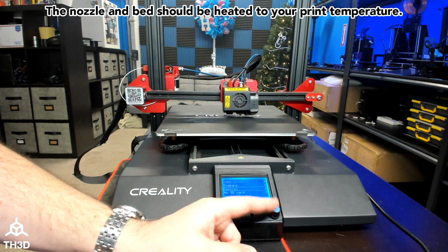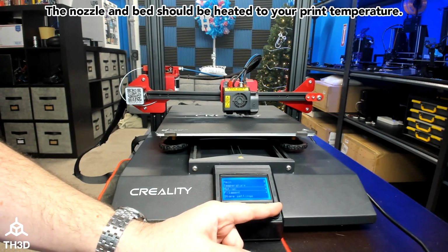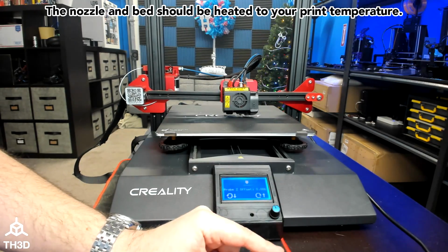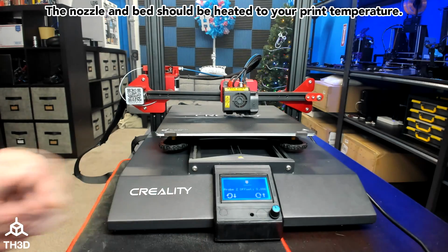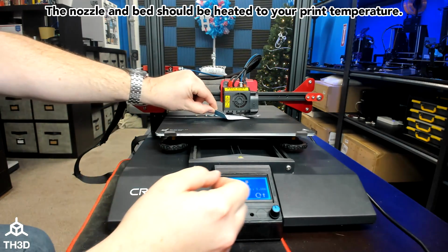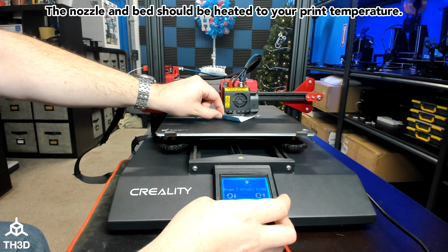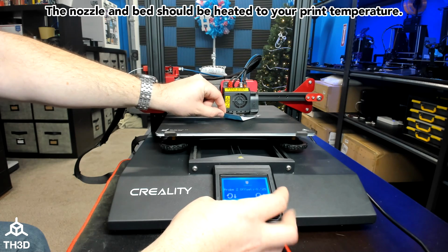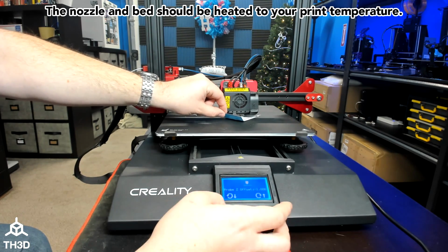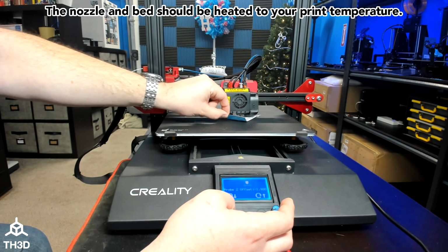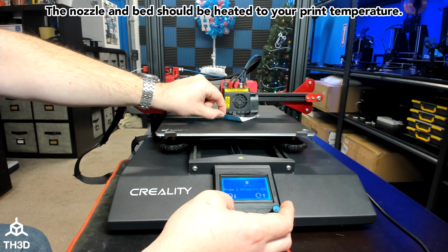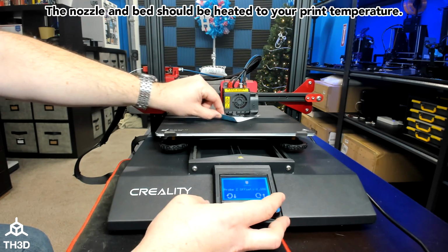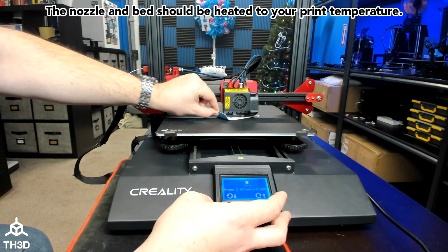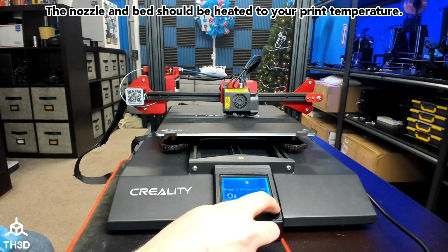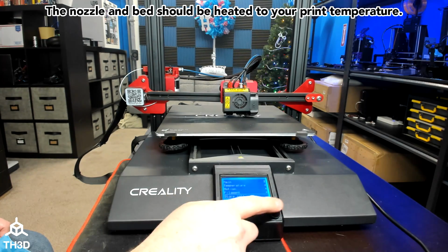and we're going to go to Control now. Go to Motion, Probe Z Offset, and now we need to grab a piece of paper. Personally, I found a business card works really well for leveling, so I'm going to use that. And now we're going to set our Z offset. I'm just moving the knob counterclockwise until it starts to grab my card. And we should have an offset of around 2 millimeters, which is what I have here. So press the button again, go back to Control, and hit Store Settings.